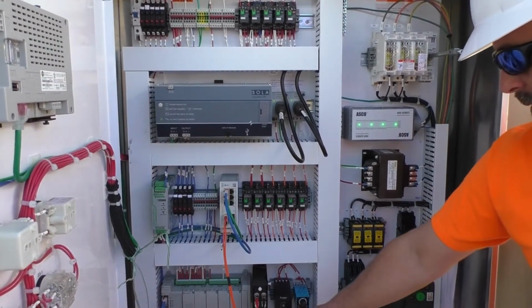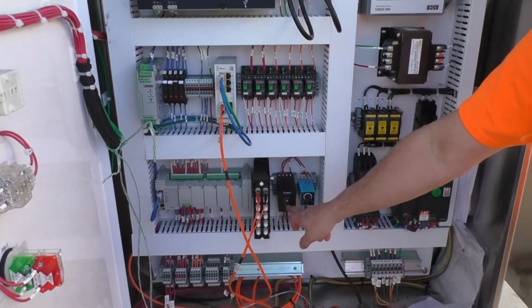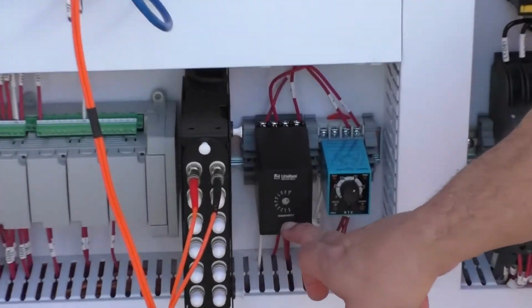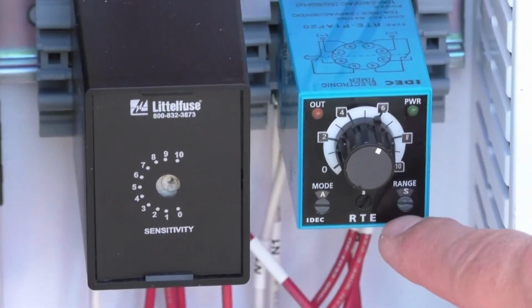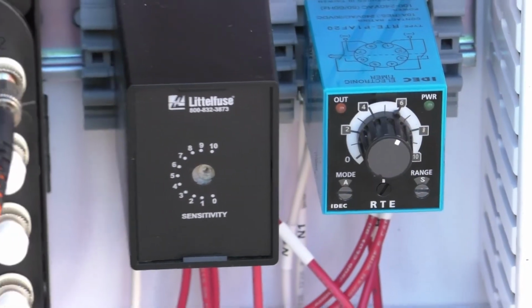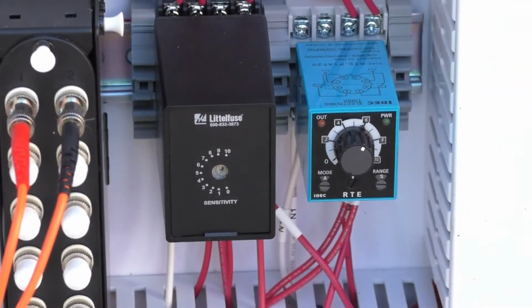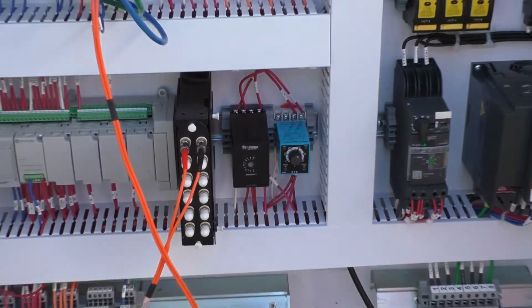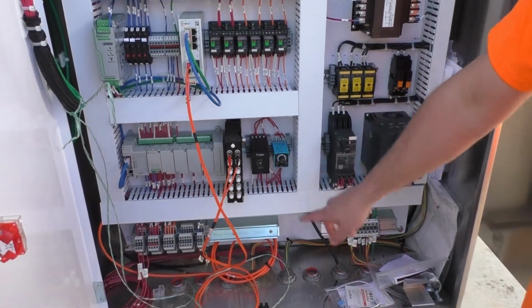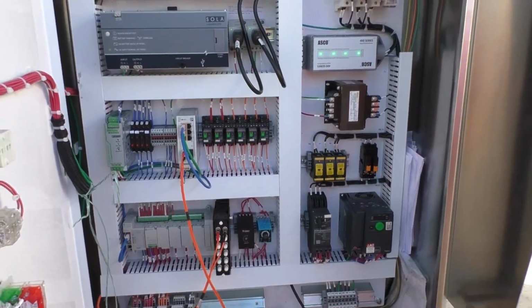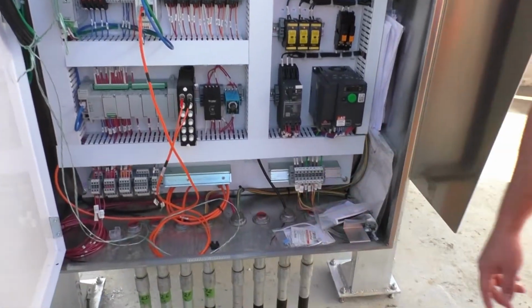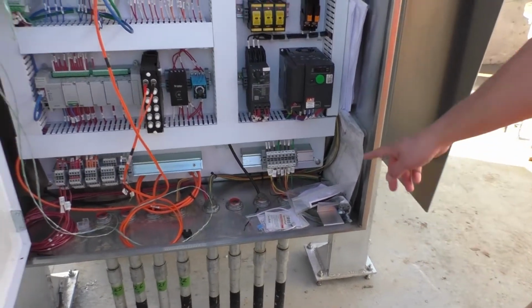This is sensitivity for your high level probe. It's set at 1. We recommend 1 or 0. This is your little delay timer for a low pressure switch that is on the backwash pipe. It's a blue box. We'll go over that in a little bit, but this is the timer right here, set for 6 seconds. Here's your leads from your backwash pump and your gear drive.